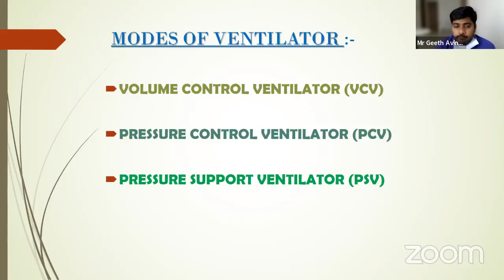So what is volume control? I just wanted to brief on these modes. Volume control ventilation is where we set a tidal volume on a constant flow. So how do we predict the volume? We have a formula called predicted body weight, which varies in males and females, and is calculated according to the height of a patient. That might be in centimeters or inches, and we have kept the centimeter formula. The formula for male is 50 plus 0.91 into height in centimeters minus 152.4, and for female it is 45.5 plus 0.91 into height in centimeters minus 152.4. So based on the predicted body weight, we adjust the tidal volumes on the ventilator.